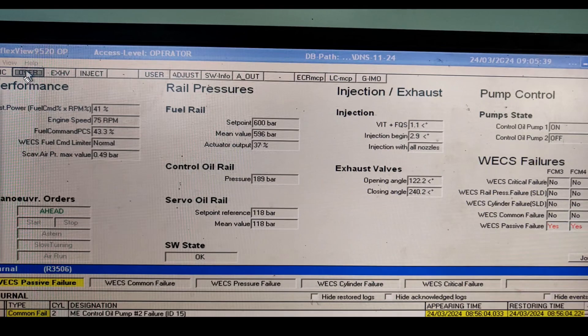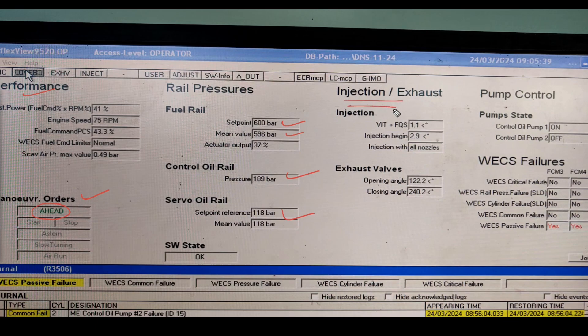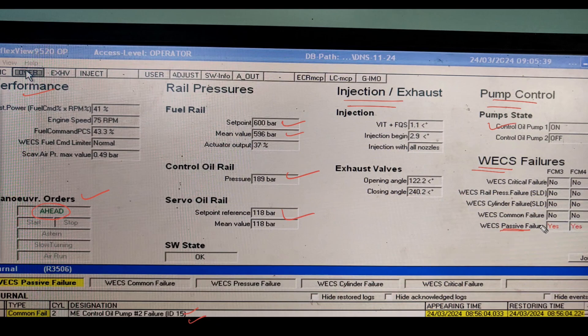Once you click on Overview, you can see the performance option - maneuvering order, engine is running ahead currently. Rail pressure mean value, control oil pressure, and servo oil pressure are shown. Injection and exhaust conditions are visible, as well as pump control - which control oil pump is running: number one is running, number two is off. Currently a passive failure is present, indicated by the alarm color, related to an oil pump problem.